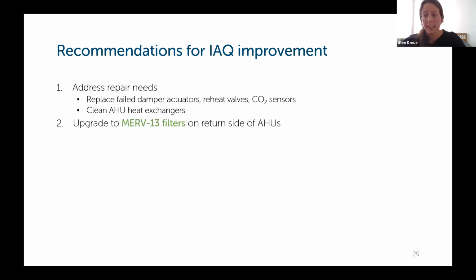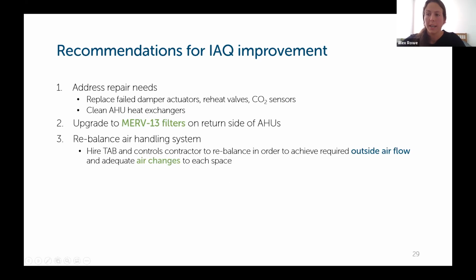Next, upgrade those MERV 8 filters in the return side of the air handling units to MERV 13 filters. And increase the frequency of changing those filters because they would likely get plugged faster due to the increased filter efficiency. Next, rebalance the air handling system in order to achieve the required outside airflow and adequate air changes, or more even air changes, in each space.